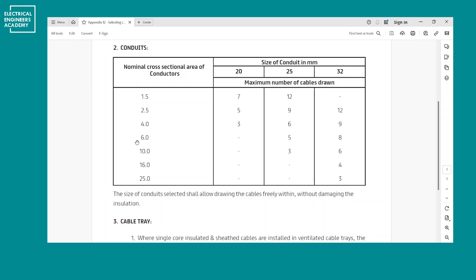For 32mm conduits, you'd typically use these for power mains going to each apartment, especially with embedded single-core wires. For example, if you're using 10mm² wires and have six of them, go with 32mm. For 16mm² wires with four conductors, 32mm works as well, though sometimes you may need to go with a bigger size.